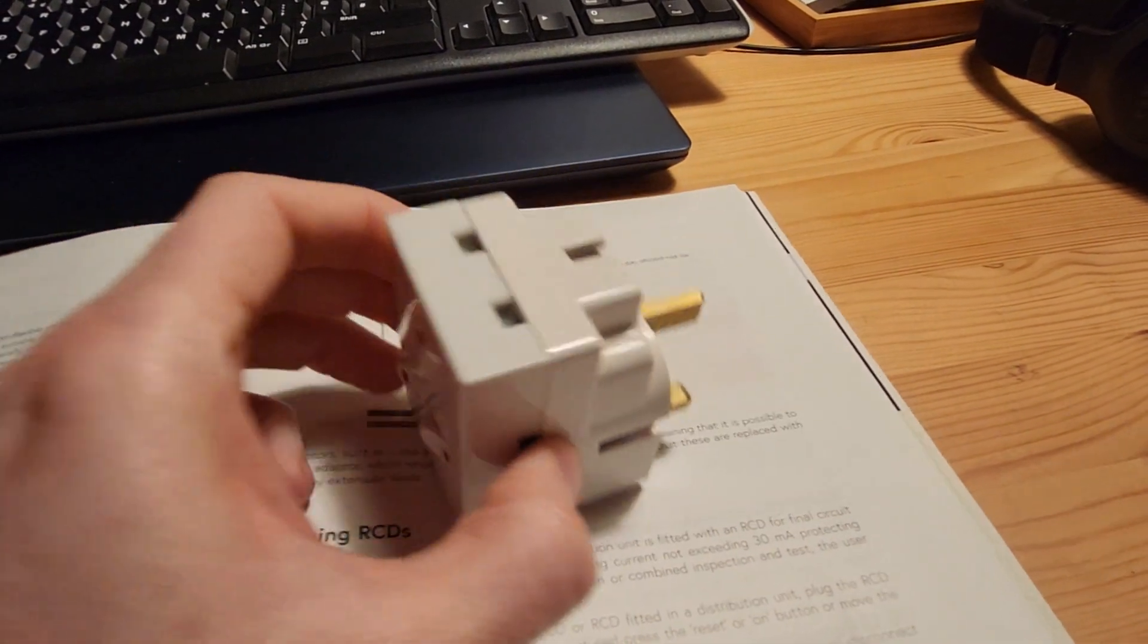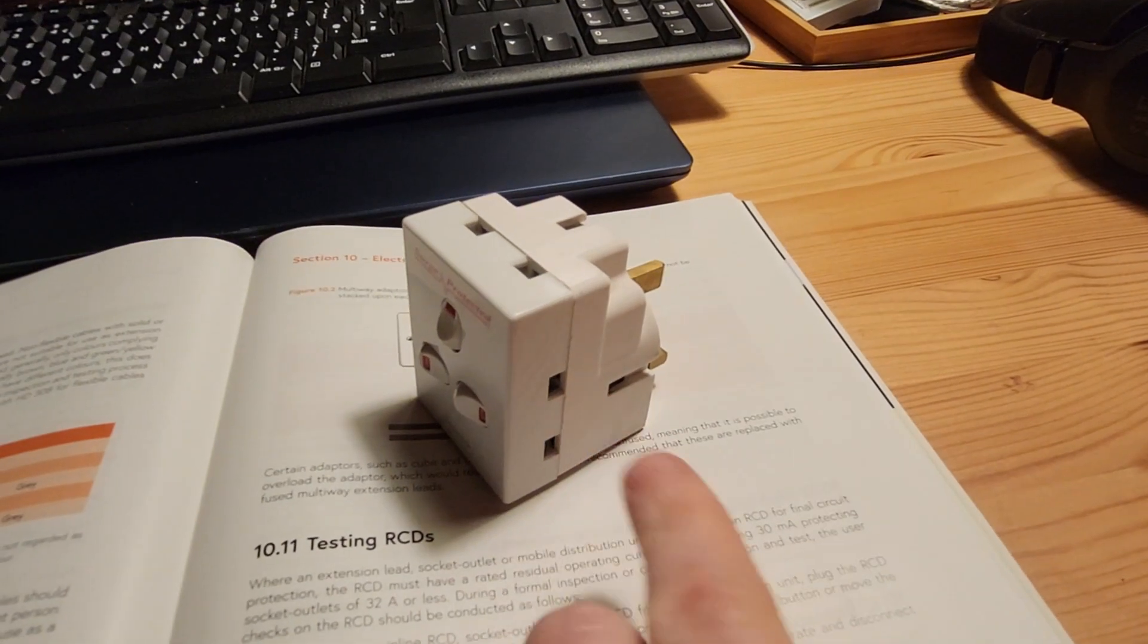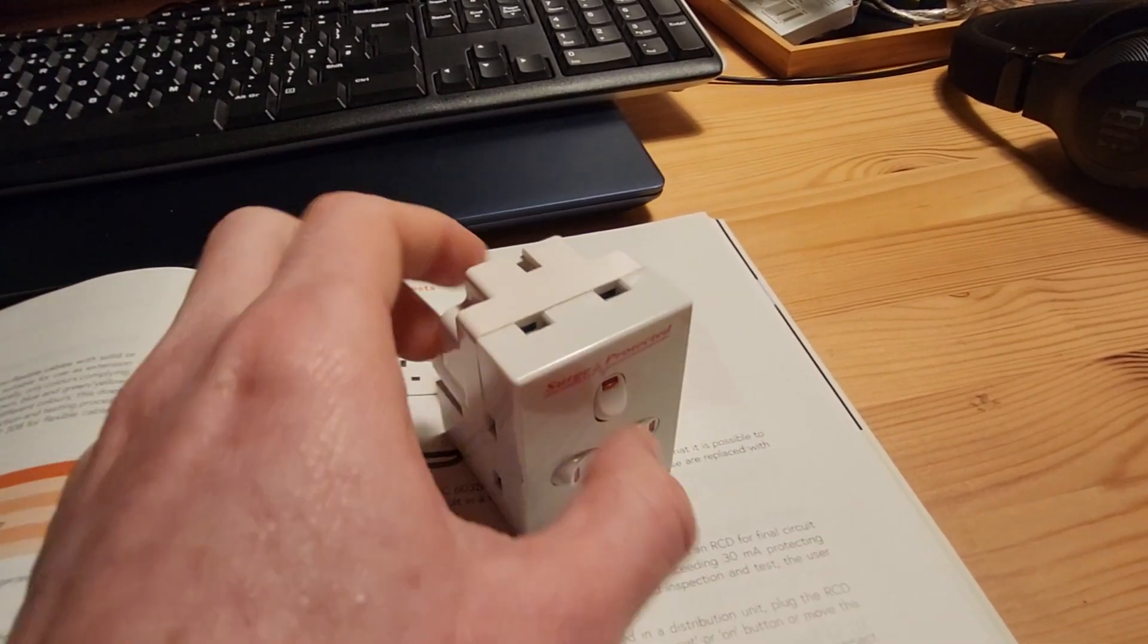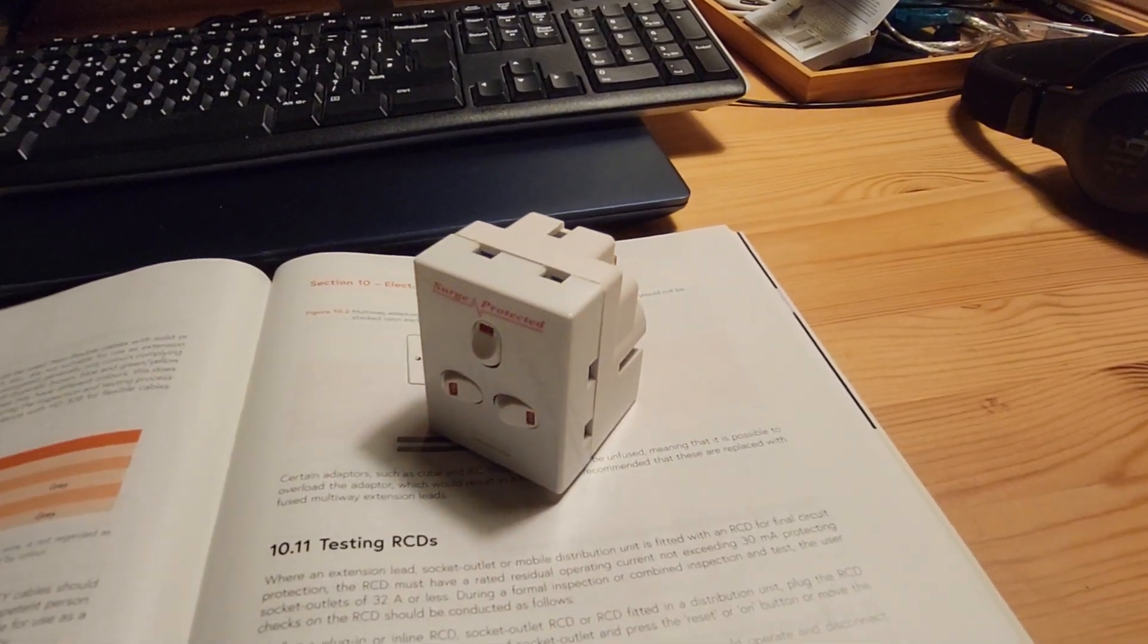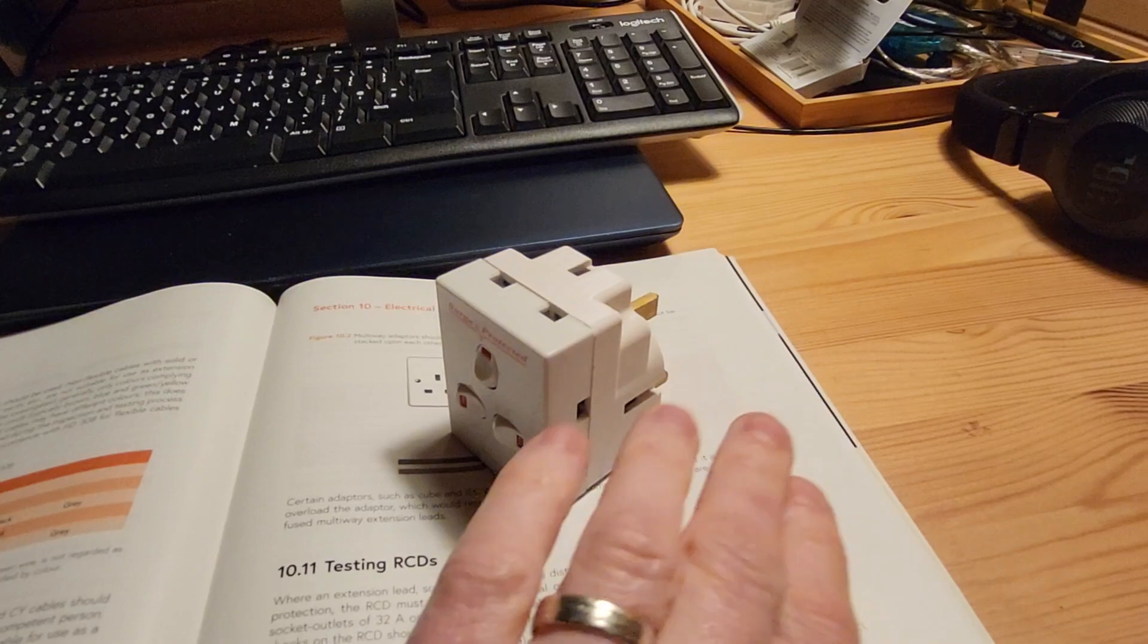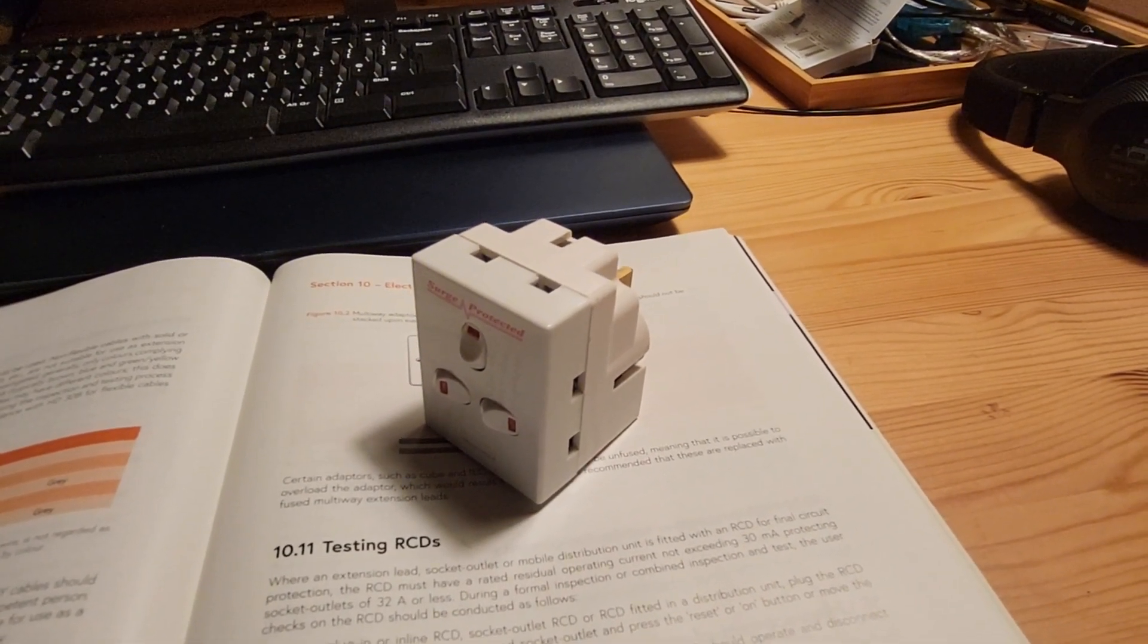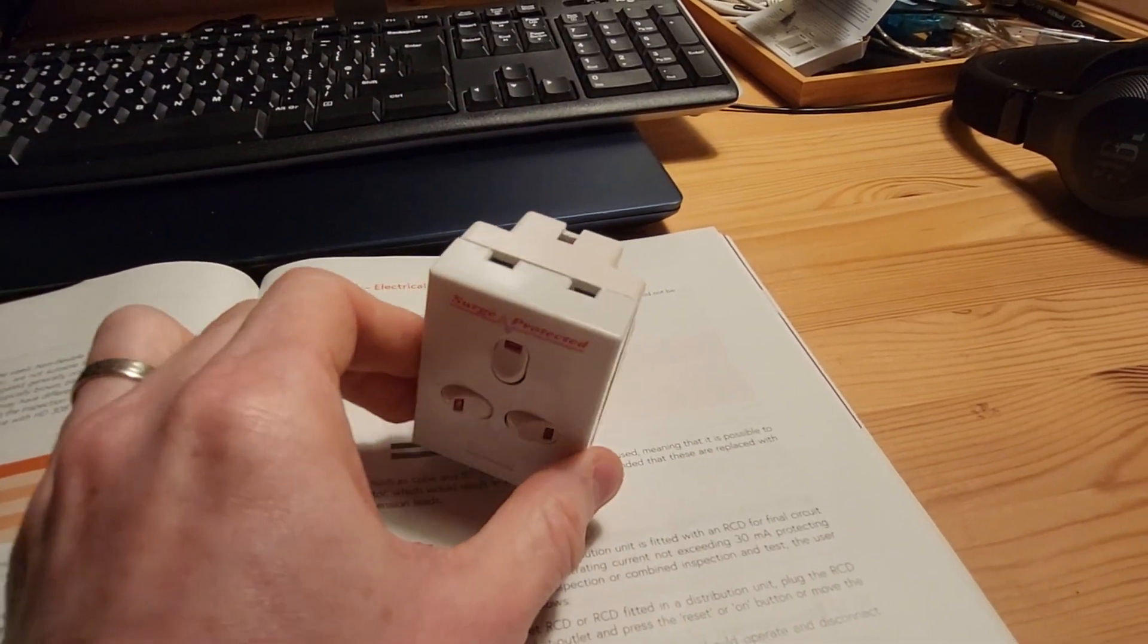I would take it out of service if at all possible. Now, sometimes if you're going into somewhere, you might have a couple of critical pieces of equipment. You might have a wireless router in there. You might have a wireless doorbell, a burglar alarm controller or something. So wherever you're going, if you're going into a rented property and you can't take it out of service straight away. So what I would then do, just for peace of mind, I would test it anyway, just to check that it's still as safe as it is intended. You've still got that earth protection and insulation and polarity and everything else. And then I would, just so you know, that then passes. But then I would also put on the notes that you recommend that it is replaced as soon as possible. But you're not able to take it out of service because it's powering a wireless internet router or something like that.